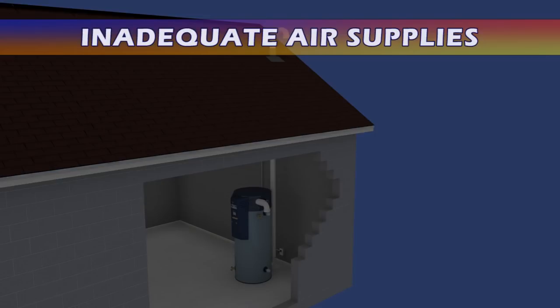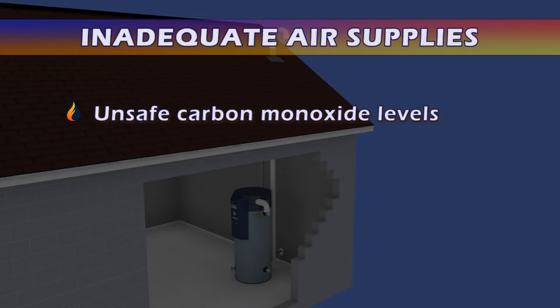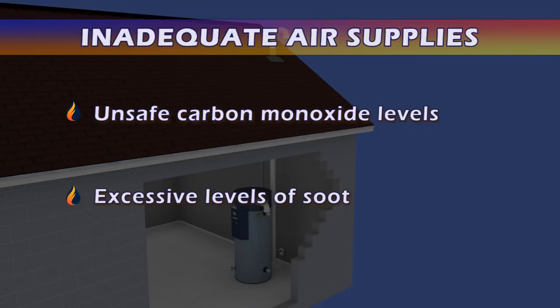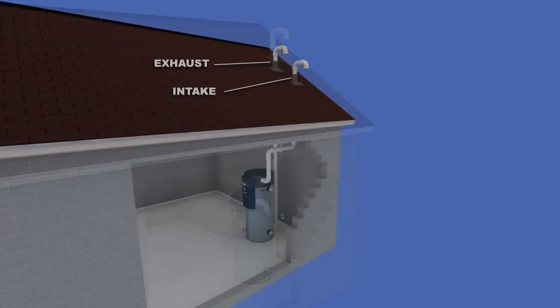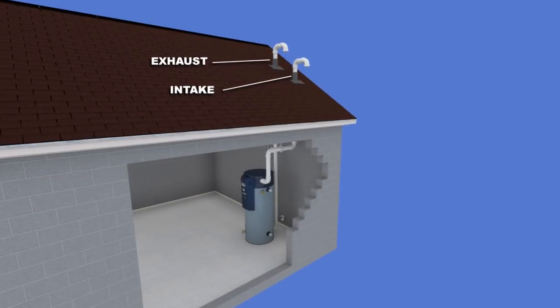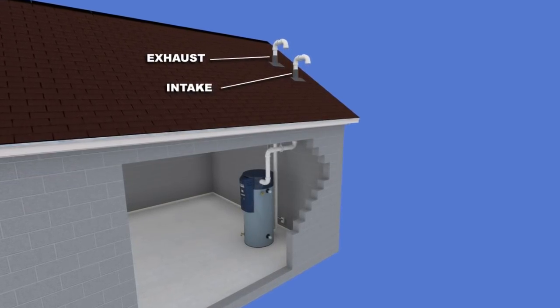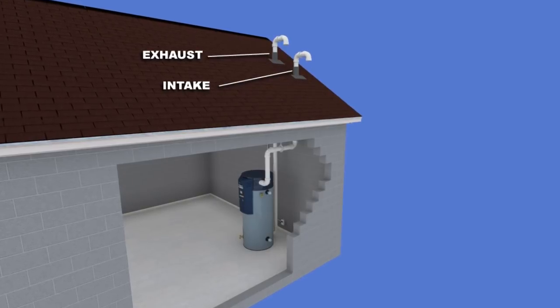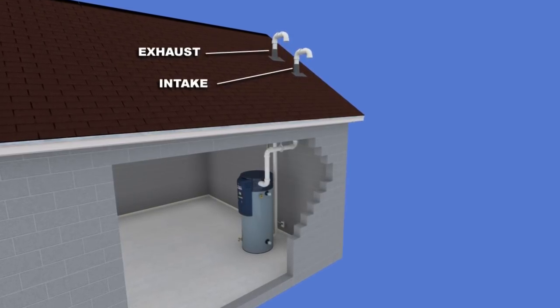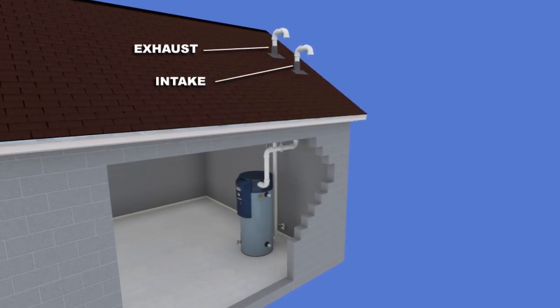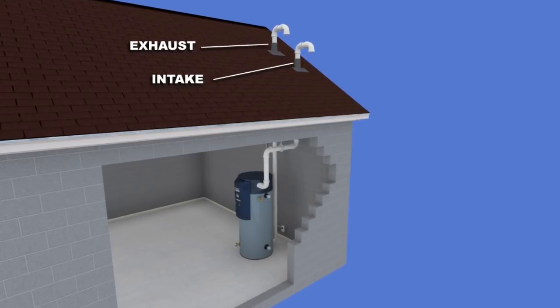Inadequate air supplies for all gas appliances may lead to dangerous conditions, such as unsafe levels of carbon monoxide and excessive levels of soot. A power direct vent system has an exhaust and an intake pipe. If a space cannot be considered unconfined, a method of directly providing combustion air, such as a power direct vent system, is necessary.